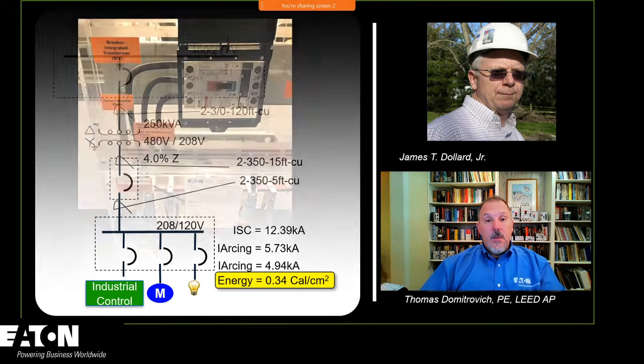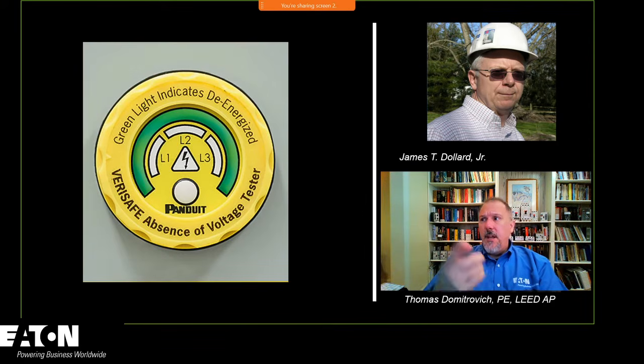And then what we did was we took that secondary breaker and we put that into the transformer directly. And that reduces the incident energy because now you're taking credit for that secondary overcurrent protective device. We have things like the arc reduction maintenance switch, where you can turn that on when you're doing energized work, or if you're doing justified energized work, and you need to reduce that level of exposure to the electrical worker. You can do that with these types of technologies.